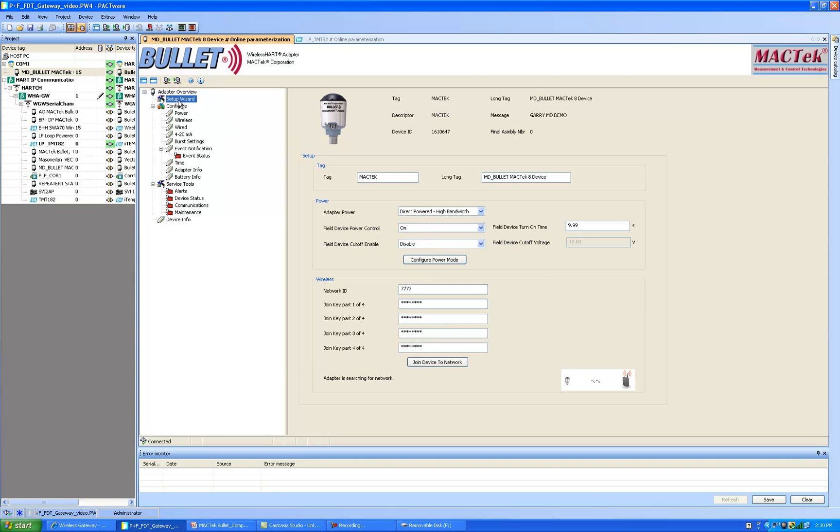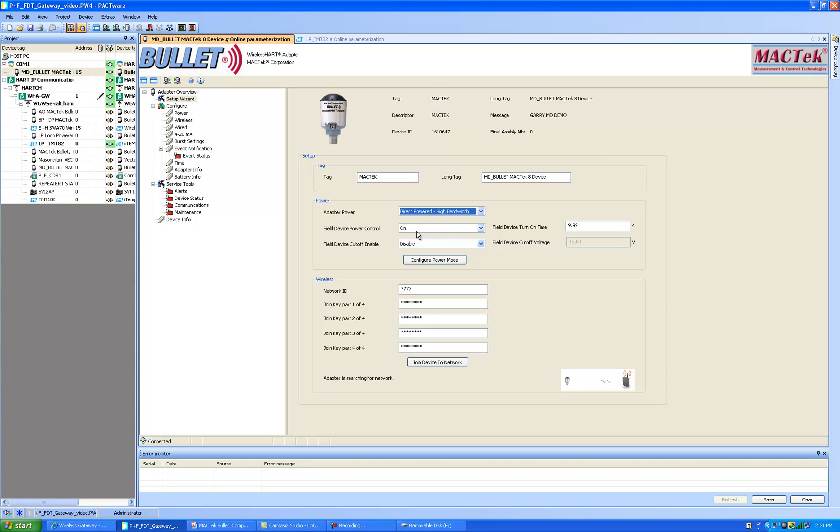How we configure the bullet is by selecting the setup wizard tab and in these fields we have the bullet tag, its short and long tag. We can configure the power. The bullet has many power options. For the eight device multi-drop I'm using a dedicated power supply. So I've selected direct power, high bandwidth, and we're turning all the devices on and we are disabling any kind of field device cutoff voltage that's typically applied when there's a battery.